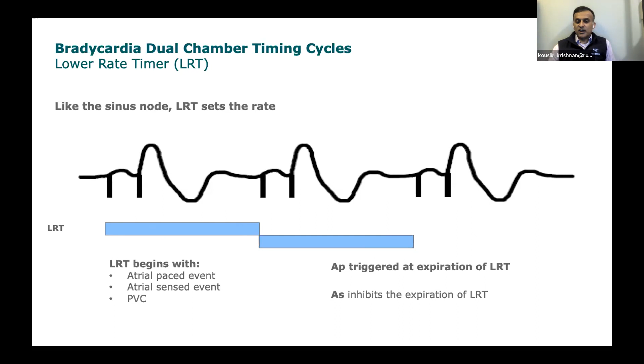Now, we also have to add in the AV delay. So even though this lower rate cannot be less than 60 beats per minute if we're setting it at 60, we now have to factor in that there is an AV delay that is going to be part of that lower rate timer. So after an A pace or an A sense, there's going to be an AV delay timer. Again, remember, the concepts are just timers getting started and stopped. So this AV delay timer is what we set it to. We might set it at 120 milliseconds or 160 milliseconds. We might set it differently if it's a sensed P wave versus a paced atrial beat. But whatever it is, we set that number, let's say, at 160 milliseconds.